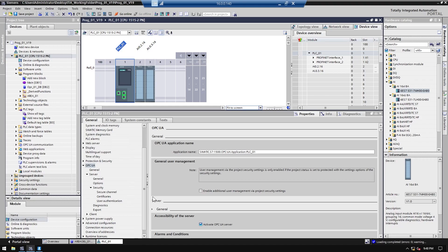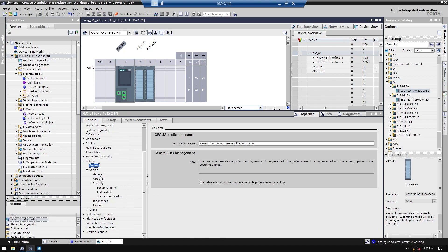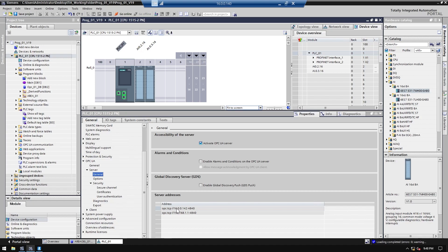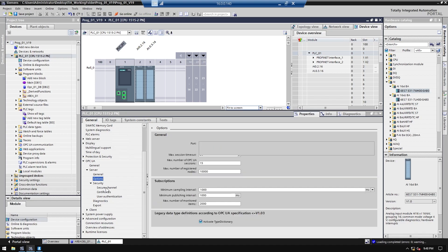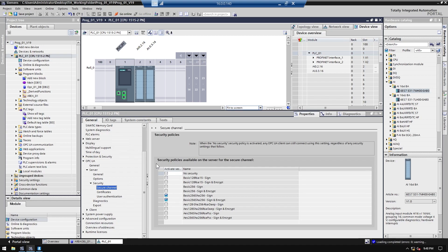The first thing we need to do is set our PLC — we have to enable the OPC UA server on the CPU. There are some things you need to configure: after activation, the IP address is set by default. This is the IP address we will access from OPC UA. For the secure channel security policies, since I don't want any unsecured connection during communication, I choose these two security policies: Basic256 — sign and sign-and-encrypt.